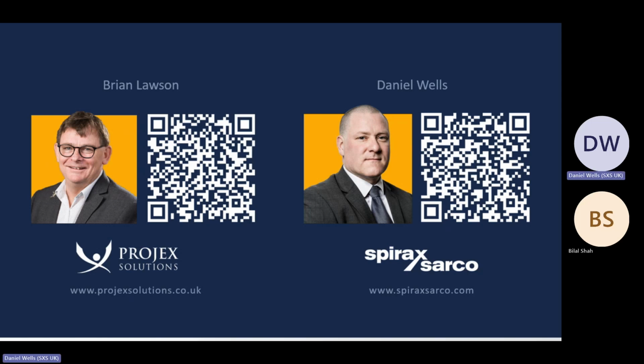So the only areas where we would really welcome superheated steam are power generation, where it's going across a turbine, because we don't want to get turbine blade erosion, or if we're distributing that steam tens of thousands of meters, like in an oil refinery. Because if we had very, very wet steam and we were moving it a significant distance, we'd have more of the erosion, corrosion, water hammer issues. We'd need more steam traps. So to generate superheated steam and move it thousands of meters, we would then de-superheat it by putting a spray of hot water into it when we get it next to the process.